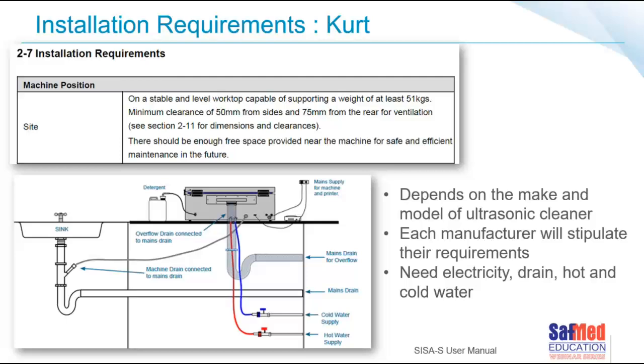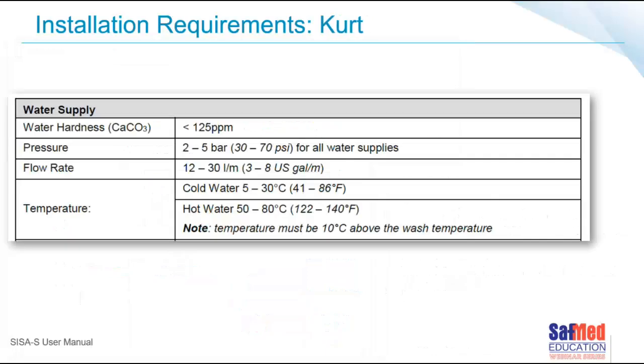What's an overflow pipe? So the overflow pipe is there in case your overflow sensor or any of the sensors overflow. Also, if your tabletop is not levelled correctly and water is filling up, it might spill out. So the overflow pipe will eliminate water spilling out over the top through the lid seal and creating any issues of water on the floor. Oh, excellent. So if there's any overfilling for some reason, or the table's a bit skew, the sensor will then activate and the water will overflow out the back into the pipe instead of coming forward or flowing onto the floor or into our CSSD. Correct. So yeah, it flows into the drain, and it's a fail-safe pipe for any of the sensors.